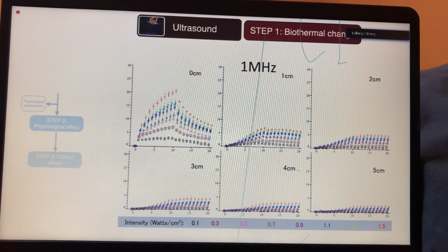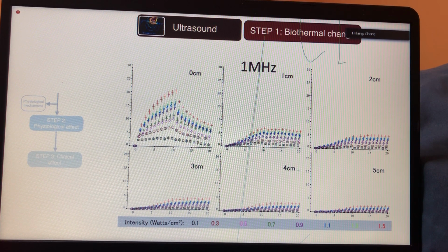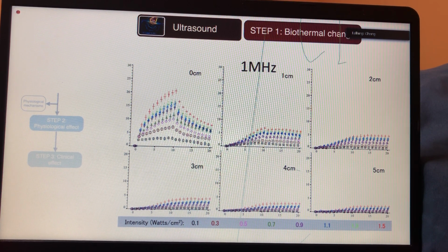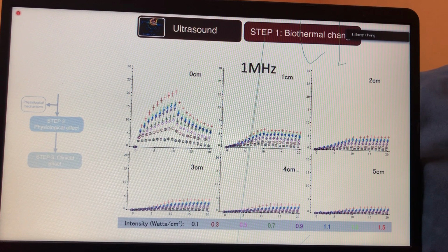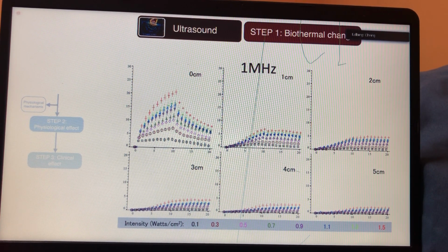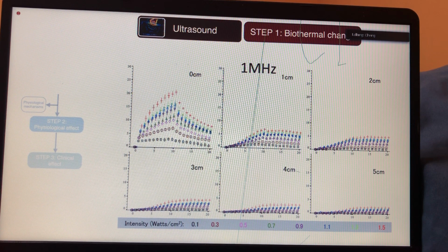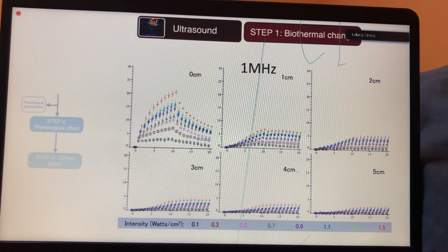But what's important is that at 1 and 2 cm, watch that carefully. It goes to the peak at 10 minutes, and after that, it doesn't drop off. It just continues to maintain that peak temperature, even after 10 minutes post-treatment. I didn't measure beyond that. If I were to measure beyond that, you would still find that it can continue to maintain that temperature for much longer, maybe 2 times, 3 times longer, 20 minutes, 30 minutes longer, perhaps. But it doesn't cool down. So 1 cm, 2 cm is the same pattern.